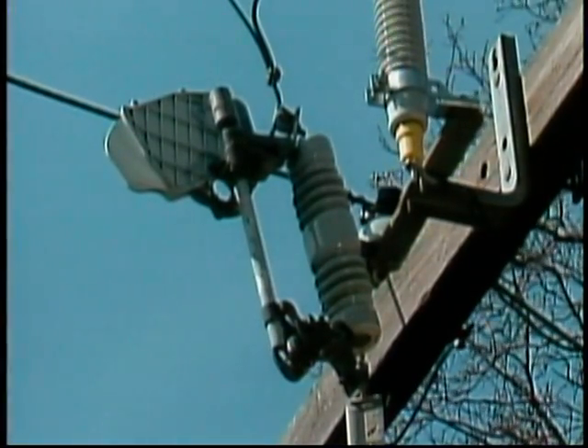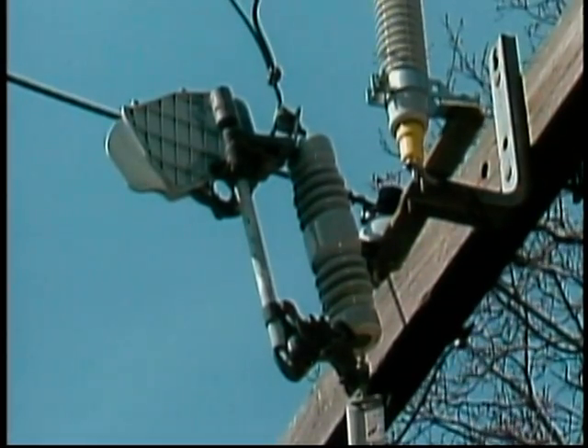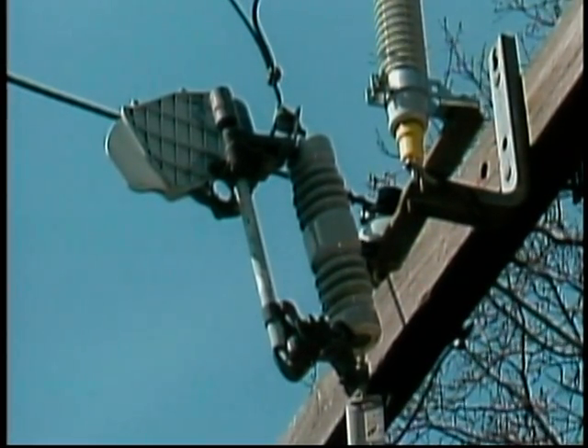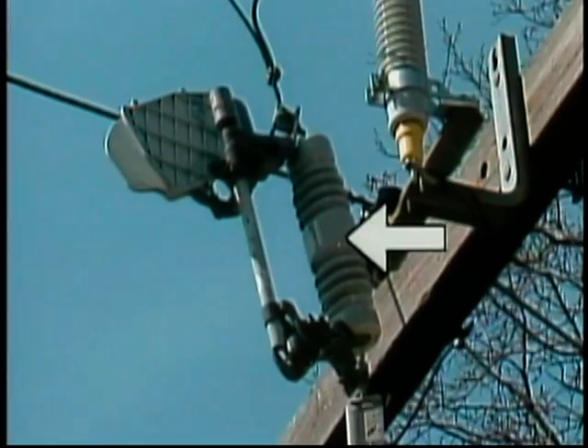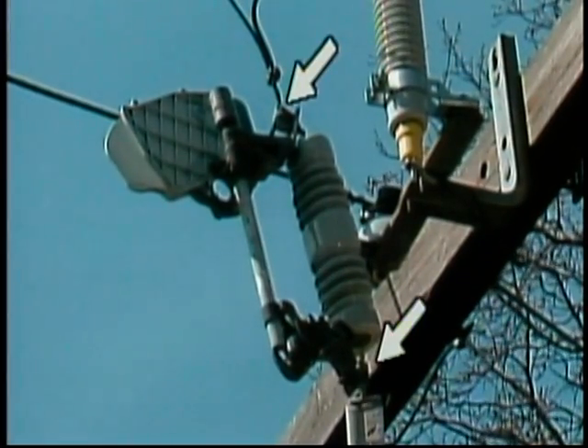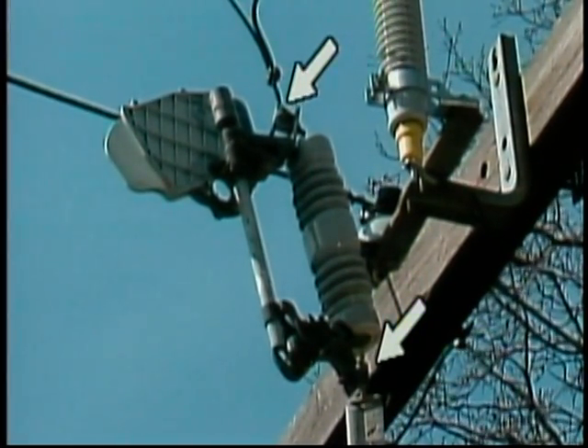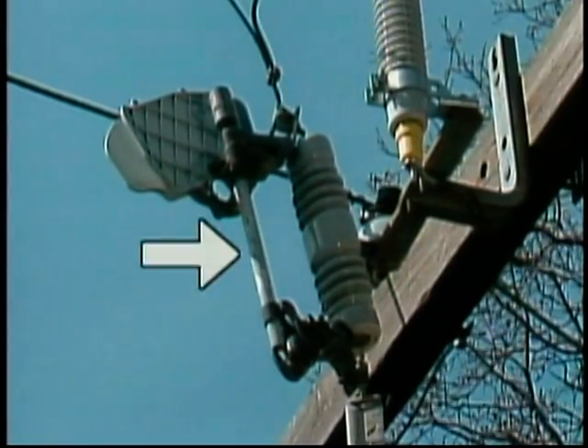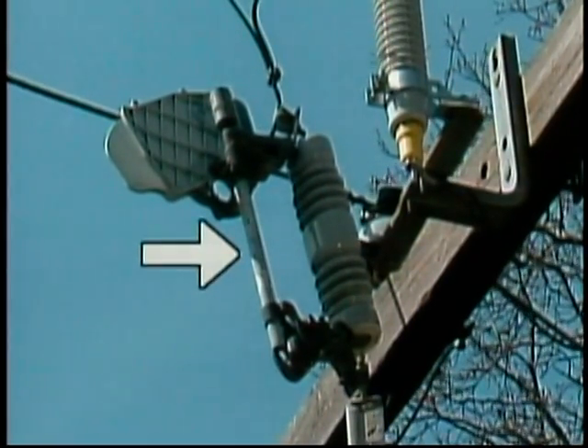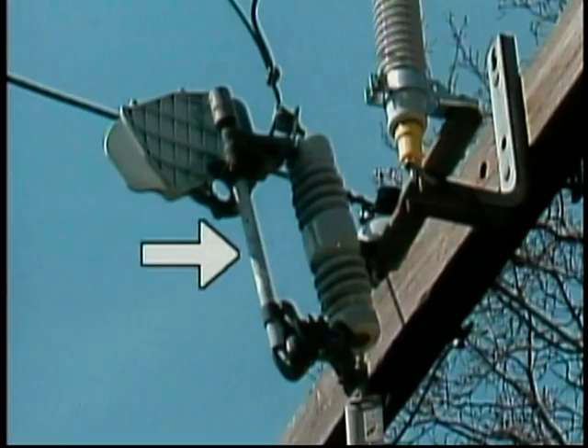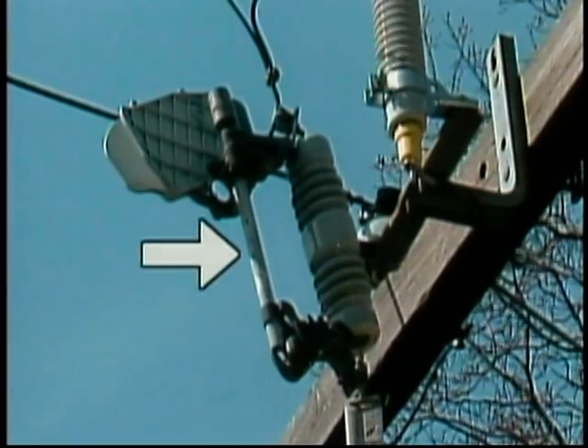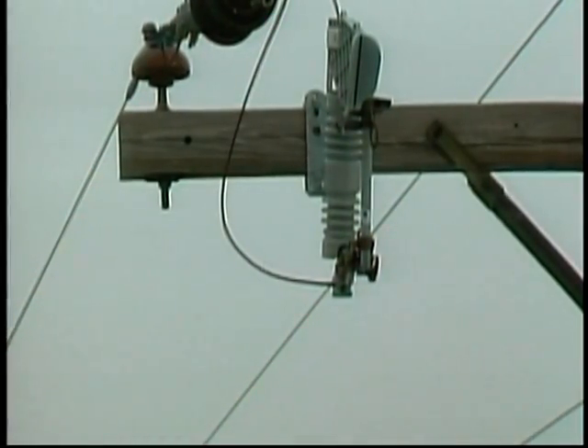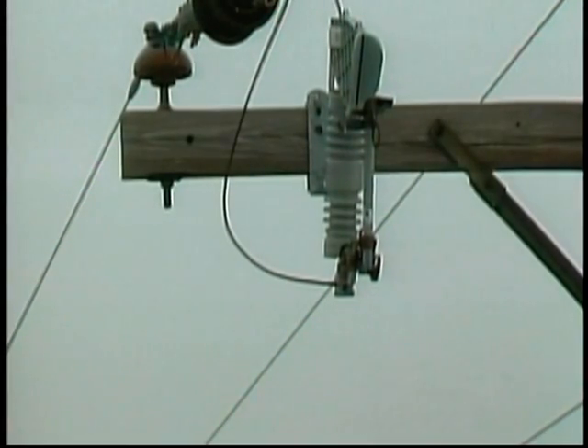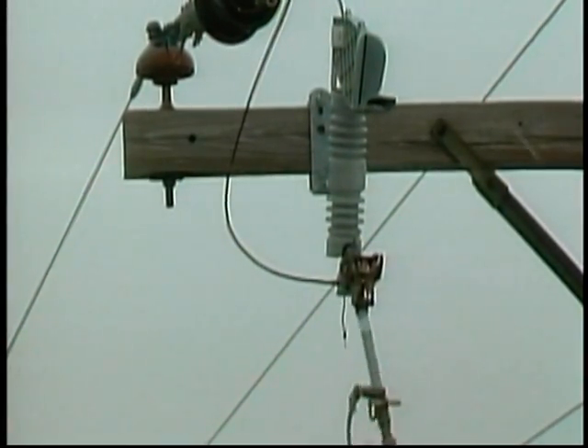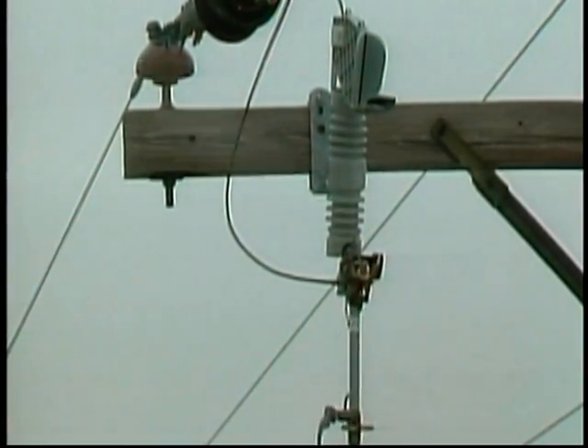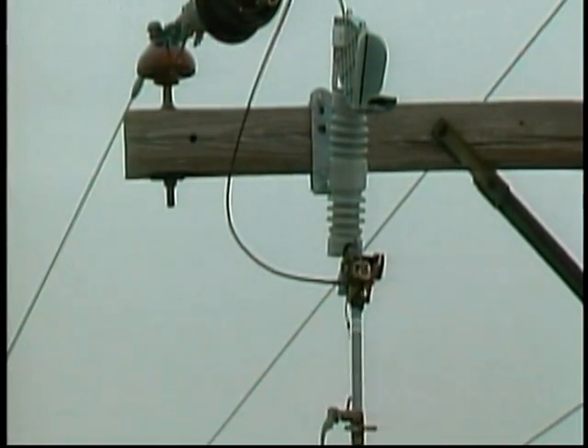Yet another protective device is the fused cutout. The fused cutout shown here includes an insulator, a contact and a connection point at each end of the insulator, and a fuse inside a fuse holder that connects the contacts and completes the circuit when the cutout is closed. When current exceeds the limit of the fuse, it will blow or break, causing the switch portion to fall open and disconnect the circuit.